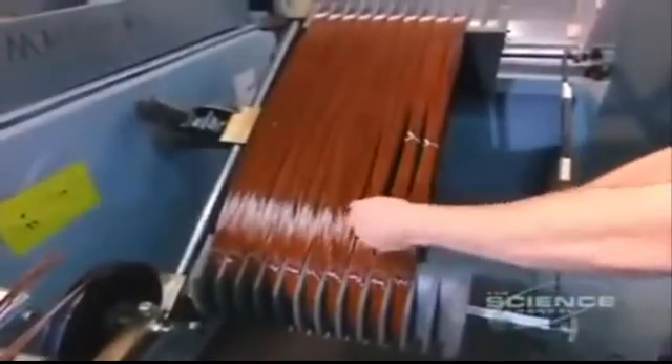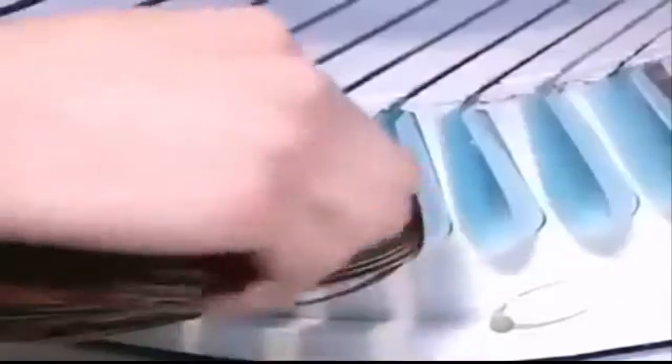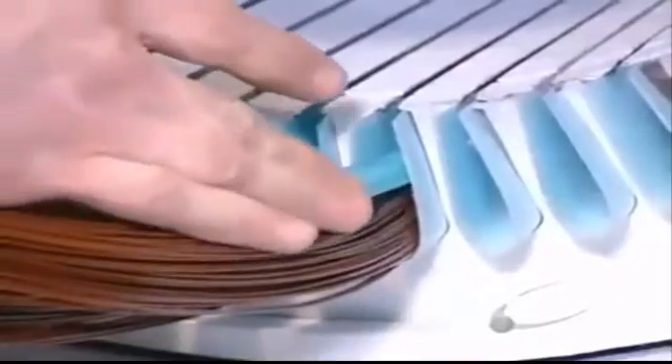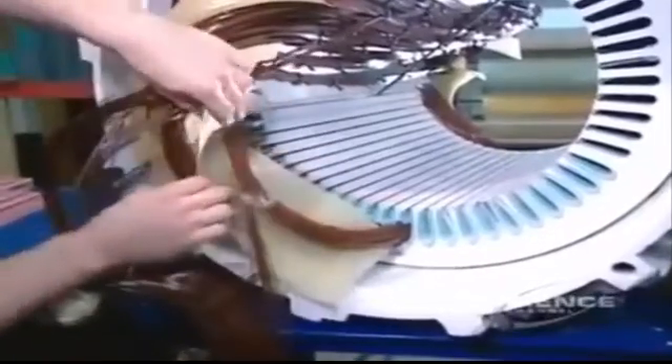Now workers tie the coils. This prevents the wires from unraveling while being inserted into the stator slots. Workers wrap each coil with fiberglass insulation, then insulate the portion of the coil left outside the slots with fiberglass sheets.